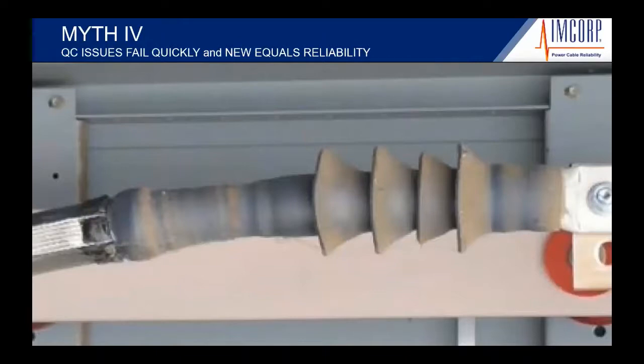Here's the QC issue. So this is a termination that's in a downstream application. It's in a refinery. Here you have a conductor, a connector, and you have a cold shrink termination, and then you have your cable. If you know what you're looking for, it doesn't take a $1 million piece of equipment to understand that you have a bad installation here. We may cut back some cables to separate the inner conductor and the outer conductor.